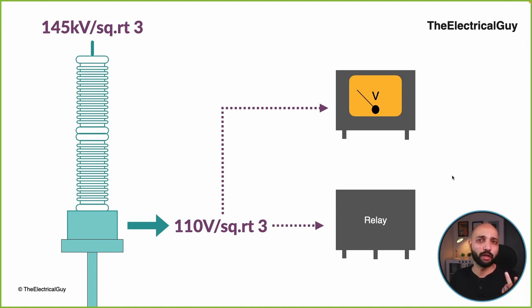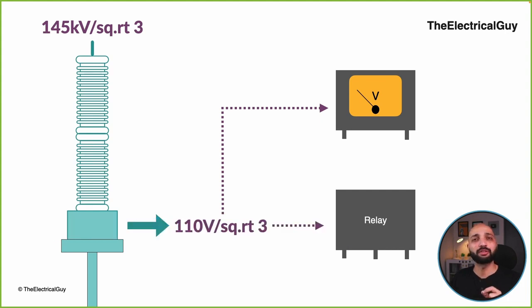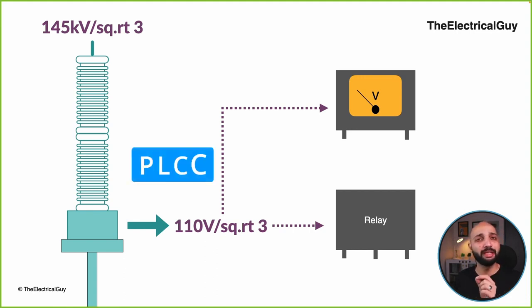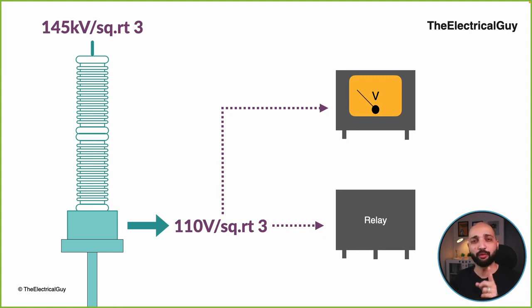Now there is one more device which is called an inductive voltage transformer, or simply the potential transformer, PT. It is called a potential transformer because it is inductive in nature. This particular device is capacitive in nature, and that is the difference. Another advantage with CVT is that it also supports power line carrier communication. It is called PLCC. It supports that function as well. What power line communication is, we will see when we talk about the wave traps.